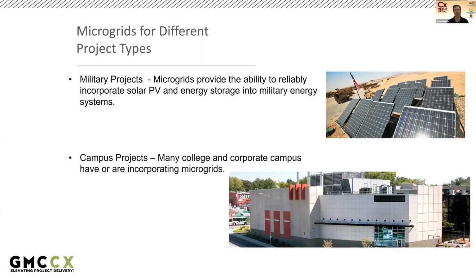Another example of a microgrid is a campus system. Not all microgrids use solar as their prime generation technology. Campus microgrids, for example, many colleges and corporate campuses, are incorporating microgrids, and they use combined heat and power, where you've got a gas turbine, which generates power with its exhaust connected to an absorption chiller for chilled water and a heat exchanger for domestic and heating hot water.